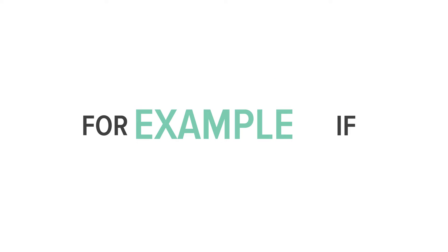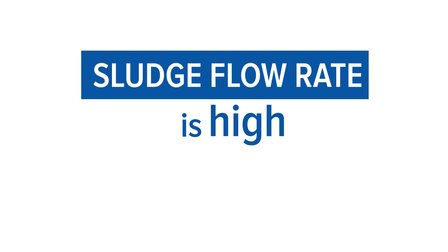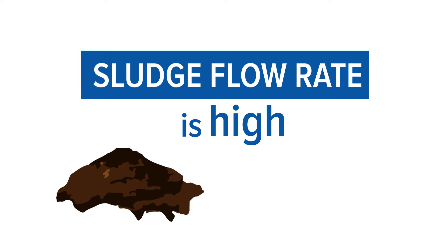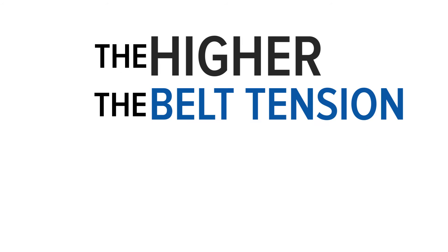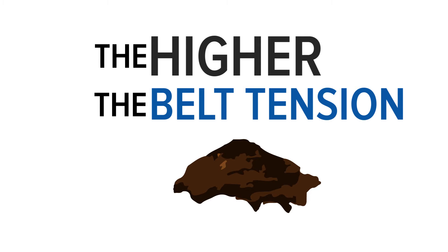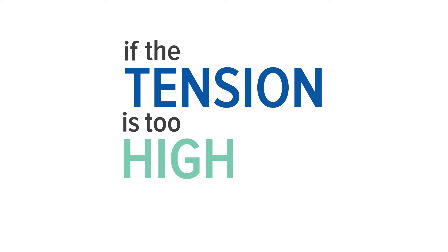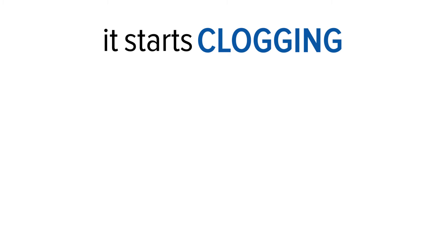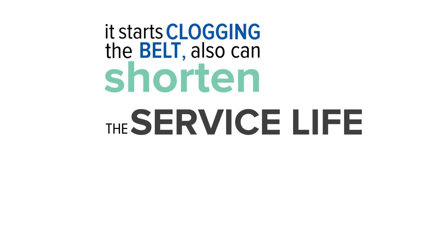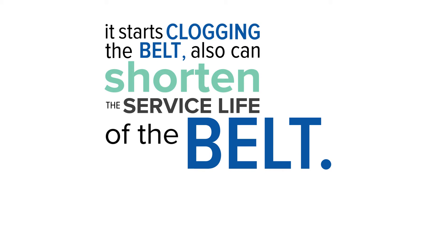For example, if the sludge feed rate is high, the solids will not be as dry. The higher the belt tension, the drier the cake will be. However, if the tension is too high, it could cause the sludge to spill out from the side, sludge clogging the belt, and it will also shorten the service life of the belt.